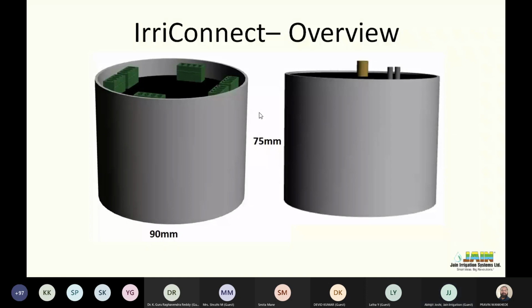Very interestingly, typically when you operate a control valve through the RTU electronically, you provide a signal, and it will operate a latching solenoid valve, which ultimately converts the electrical signal into a hydraulic one, and hydraulically your valve is operated. While doing so, sometimes if the solenoid does not operate, or if some dirt is accumulated in the hydraulic channels of the RTU, or for any reason the valve does not operate, there was no way to know - electronically, you would see on your dashboard that the valve is in operation, but practically in the field the valve was not actually operating. We saw and experienced this kind of issue.